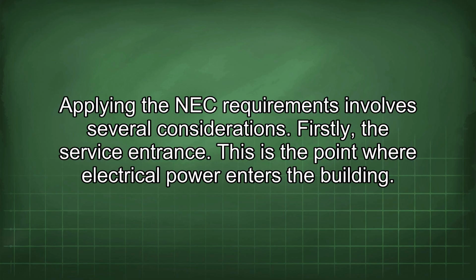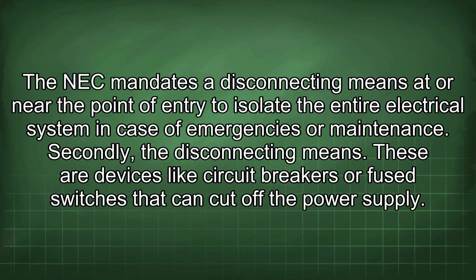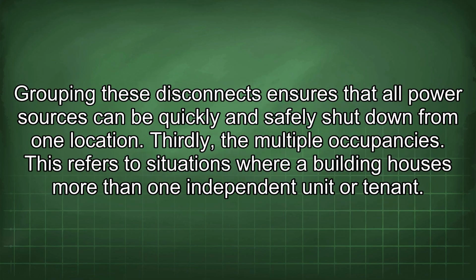Firstly, the service entrance. This is the point where electrical power enters the building. The NEC mandates a disconnecting means at or near the point of entry to isolate the entire electrical system in case of emergencies or maintenance. Secondly, the disconnecting means. These are devices like circuit breakers or fused switches that can cut off the power supply. Grouping these disconnects ensures that all power sources can be quickly and safely shut down from one location.